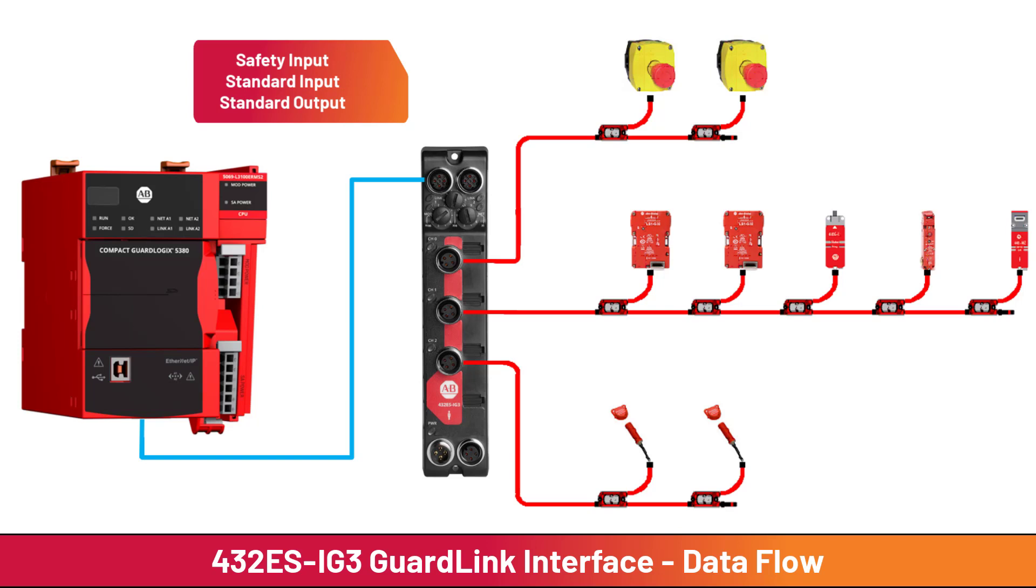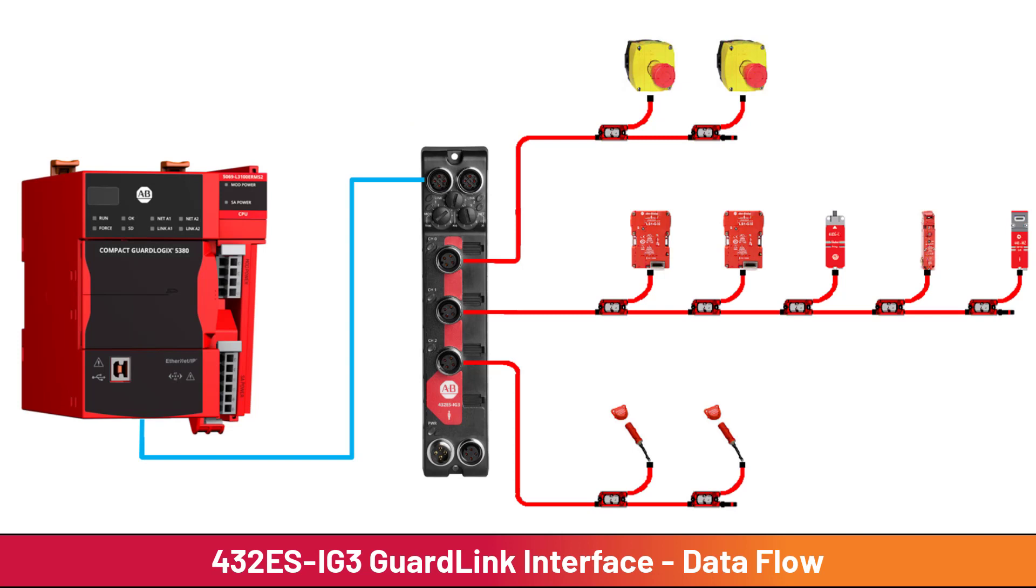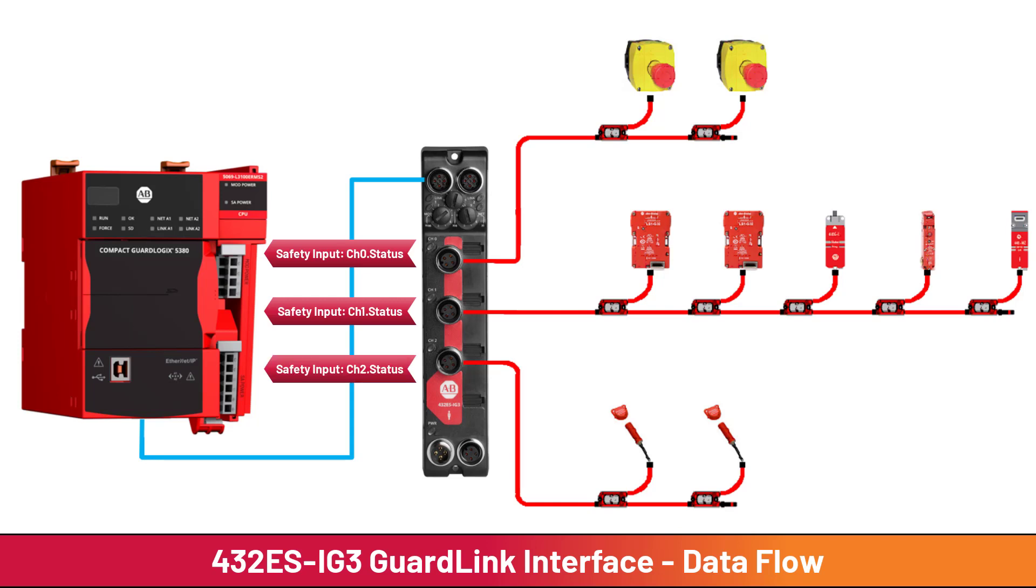The first type of data is safety input data. There are three bits of safety rated data coming from the GuardLink interface: channel 0 status, channel 1 status, and channel 2 status. The channel status data can be used in the safety task for safety functions.